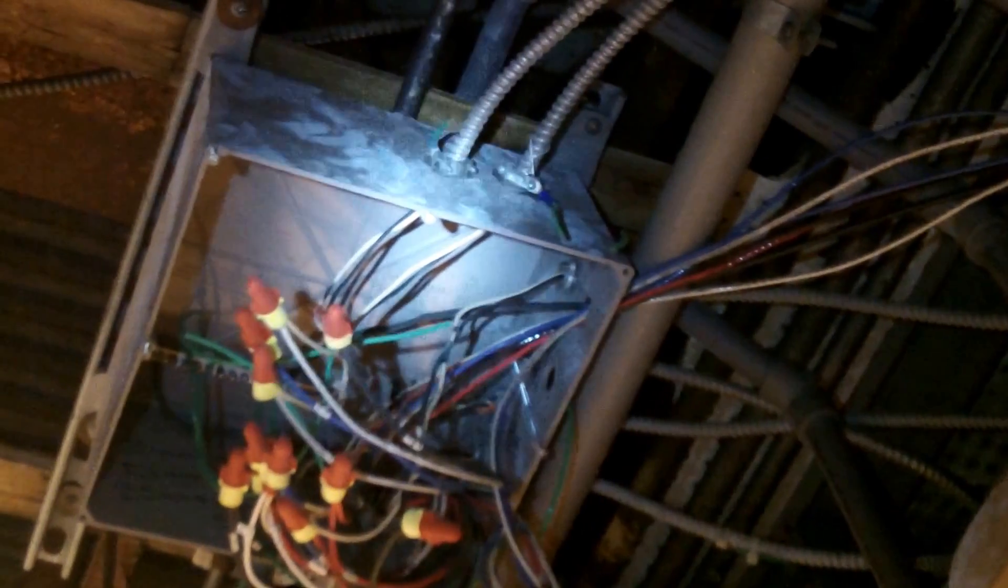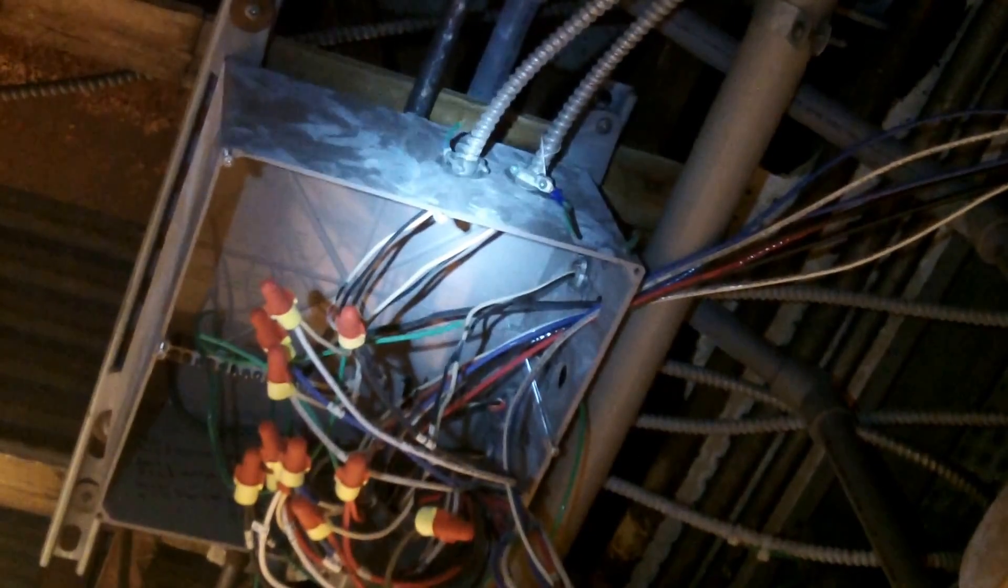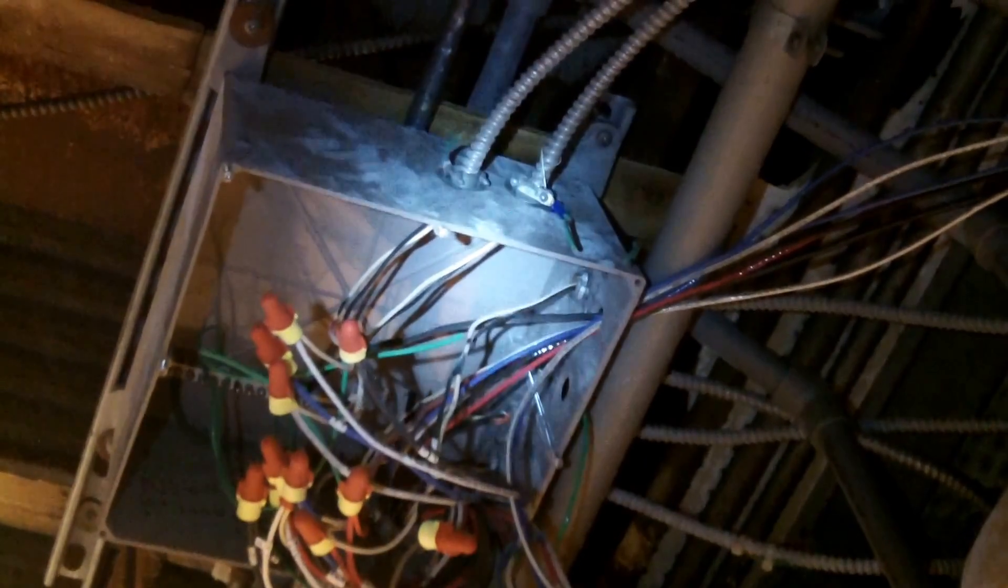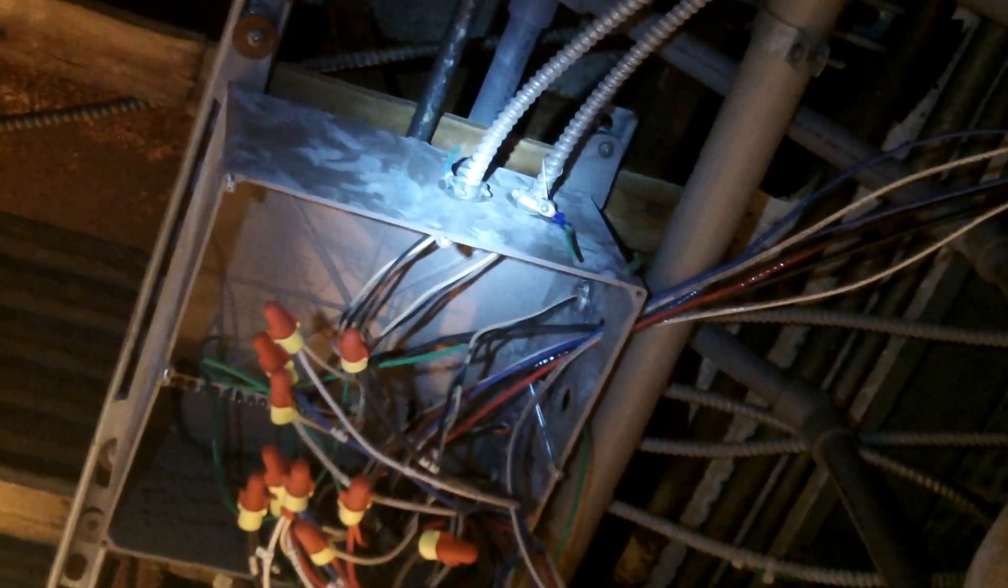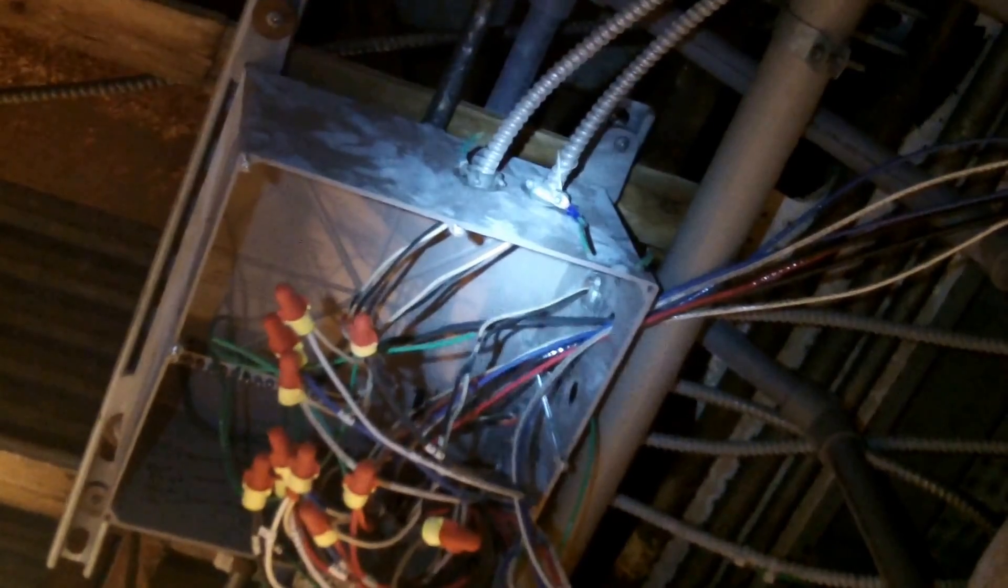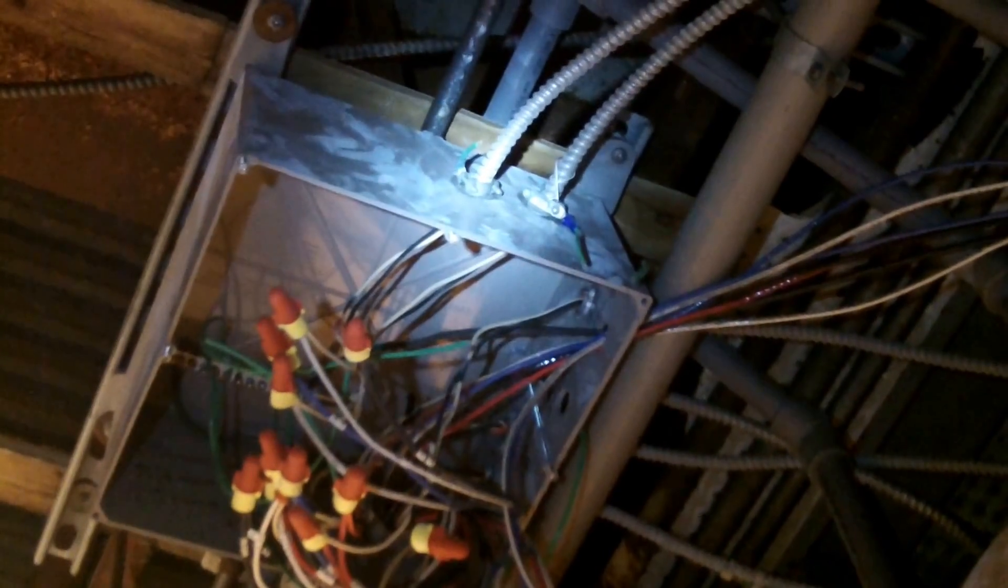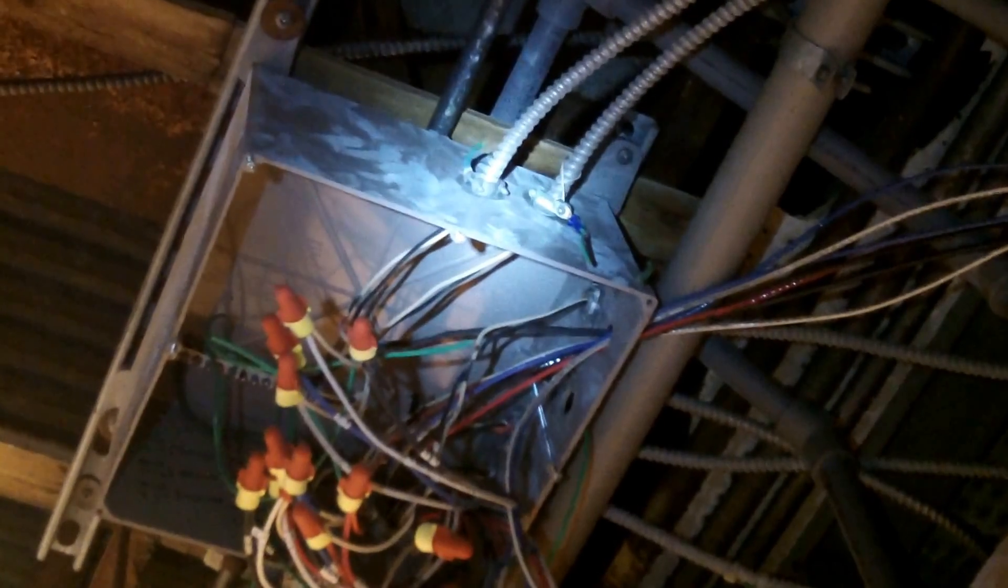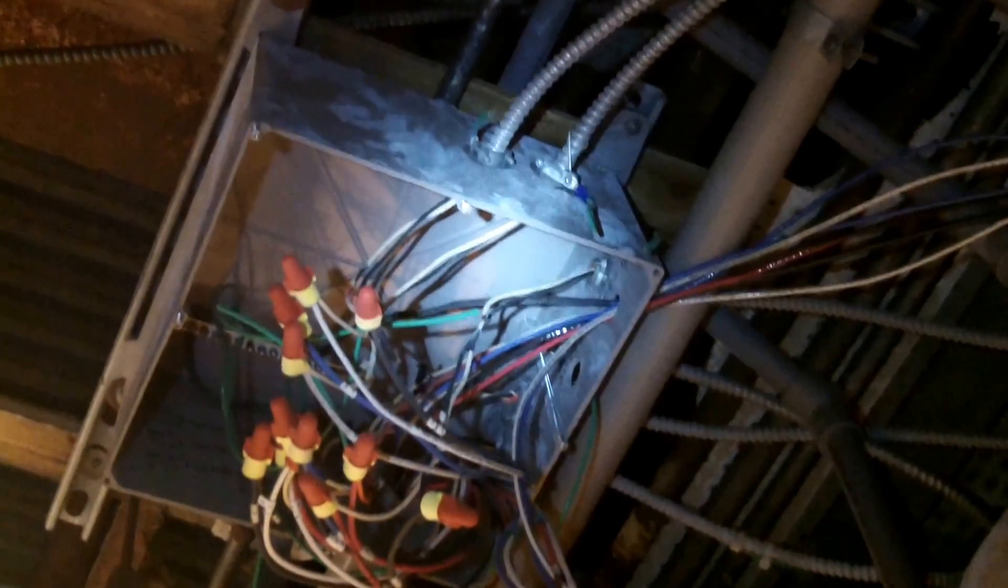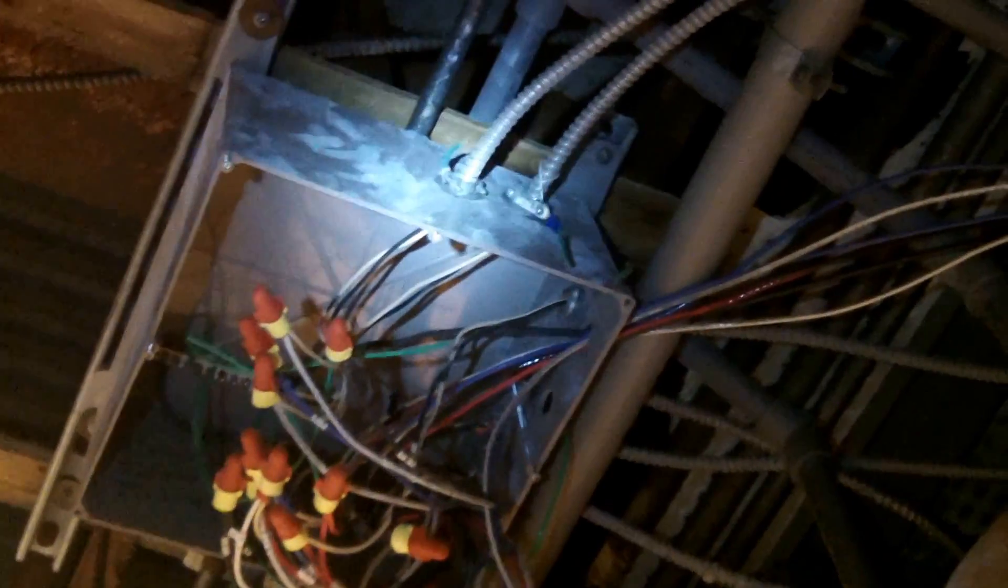This is not permitted in section 314.3. However, there is an exception that does allow these AC cables and metal pipes to be used with a non-metallic box if there's an internal bonding means to bond all of the cables and pipes together on the inside of the box.